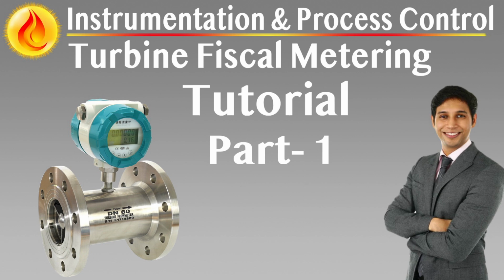Sphere guidance and wear prevention. Guide bars or tees must be designed to center the sphere reliably without inducing damage, deflection, or deformation. These mechanical elements must be optimized to maintain contact without abrasion and to prevent misalignment during high-flow proving runs. Their geometry must be compatible with the prover's bore and sphere design to avoid false detector actuation or wear-induced errors.